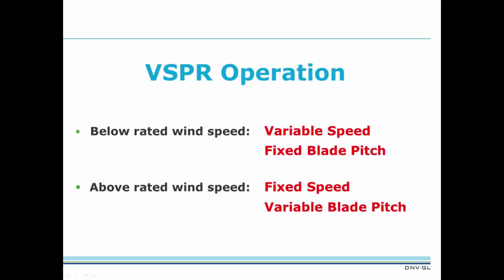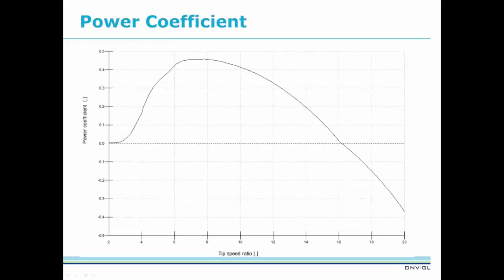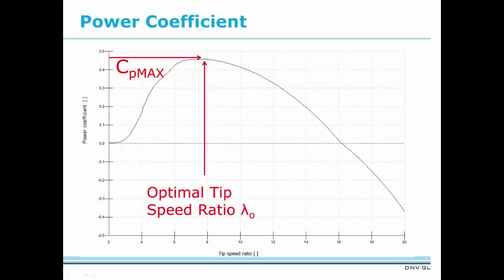Let's start by looking at operation below rated wind speed. This is variable speed operation and we'll be introducing the term optimal mode gain. At wind speeds below rated, the goal is to capture as much energy as possible by maximizing the power coefficient. To do this, the tip speed ratio must be kept constant at the optimal value. This is only possible if the speed of the rotor can change as wind speed changes.